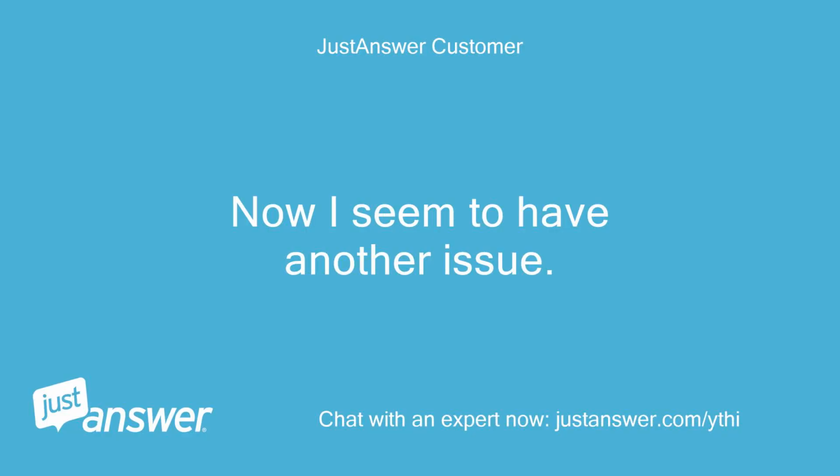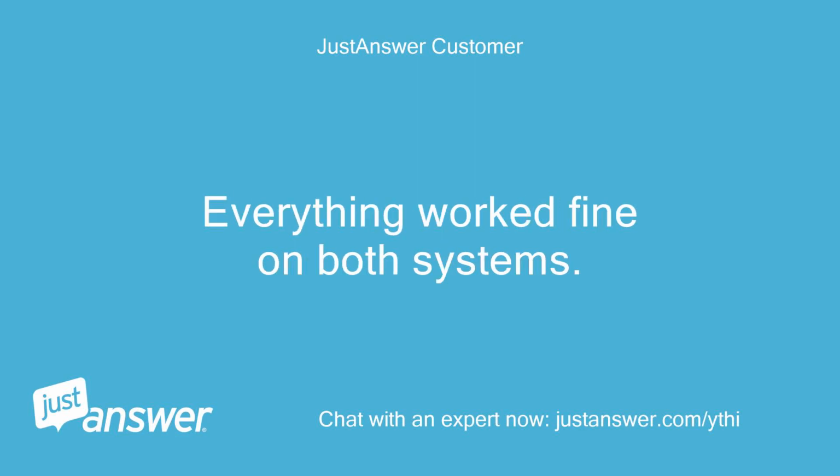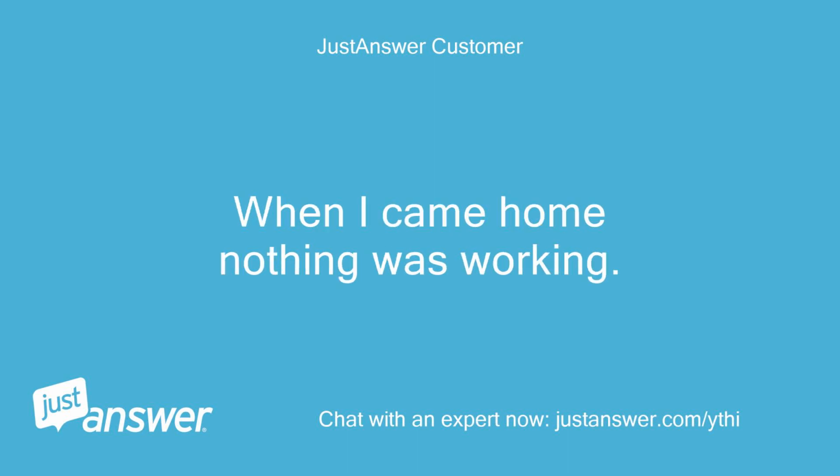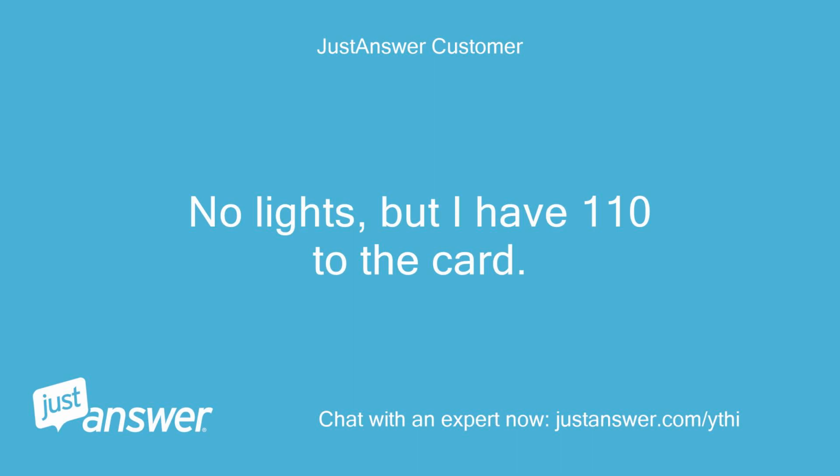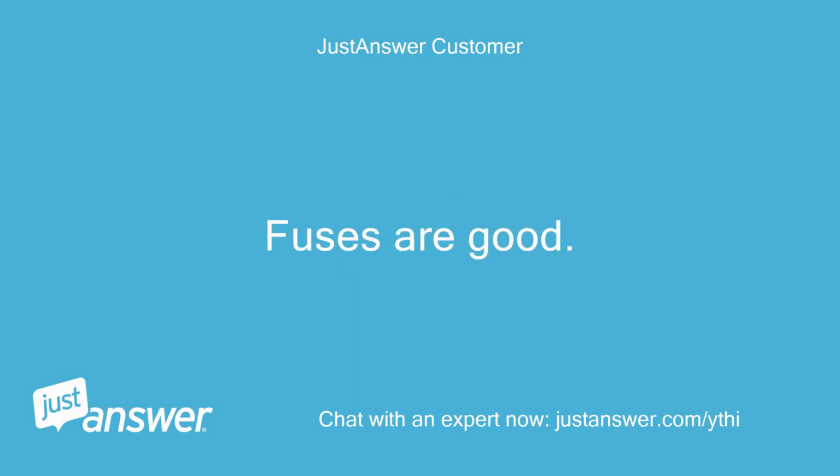Now I seem to have another issue. Everything worked fine on both systems. When I came home, nothing was working. The unit was dead. No lights, but I have 110 to the card. Fuses are good.